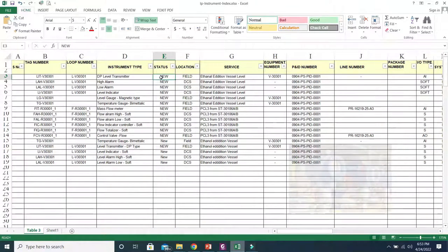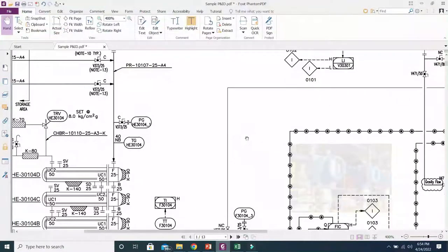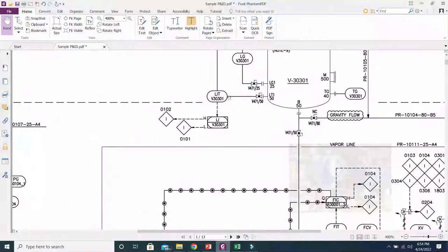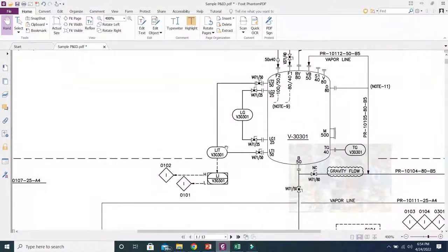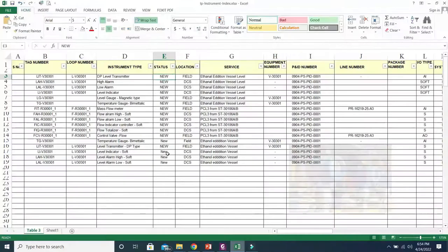Location defines the exact location of any particular item. Like any instrument which is in the field, its location will be field. Suppose there is a level transmitter as mentioned in this P&ID. This level transmitter will be in the field, but its signal will not be in the field. So you can say the level transmitter location is in the field, but its alarm is in the DCS or in the control system. This way we can define the location.